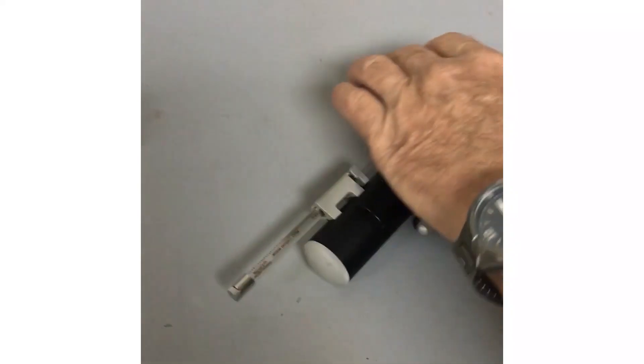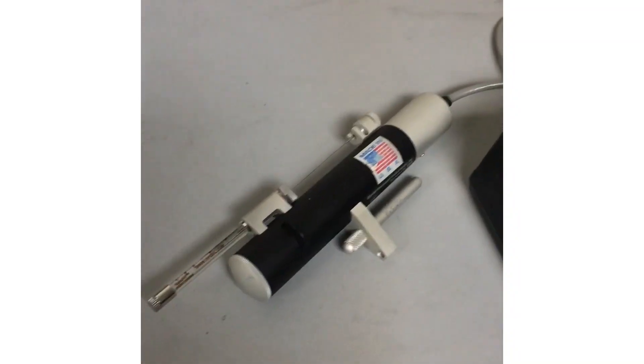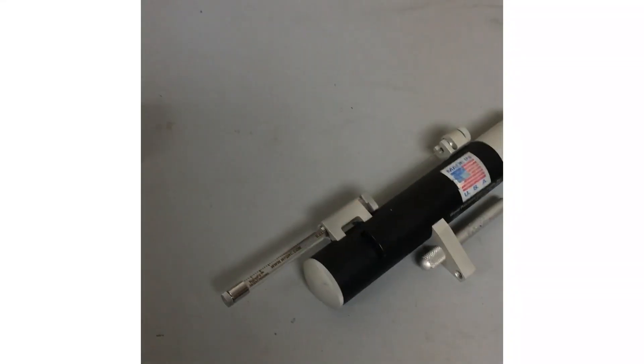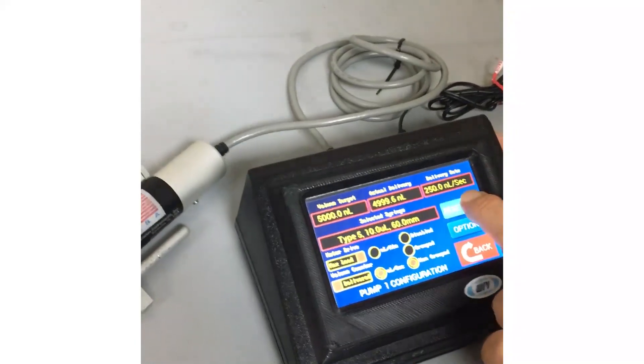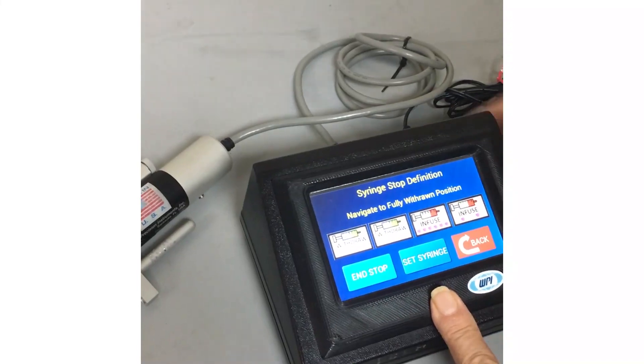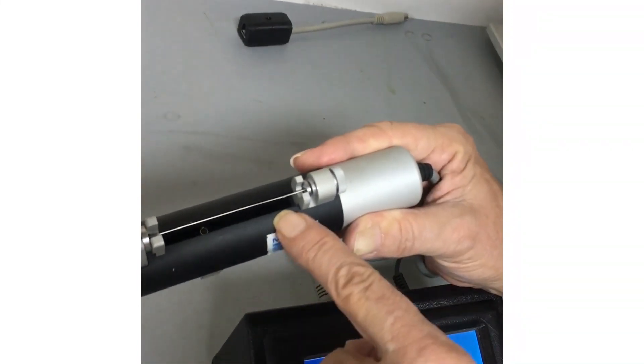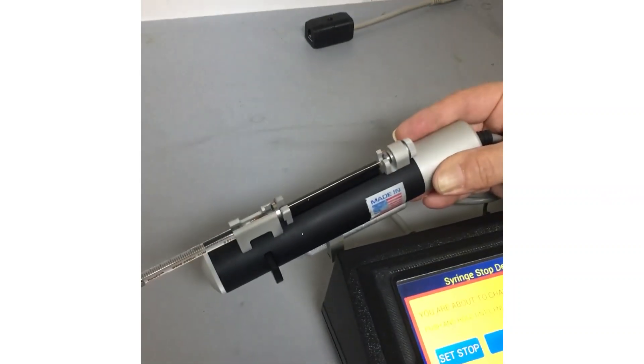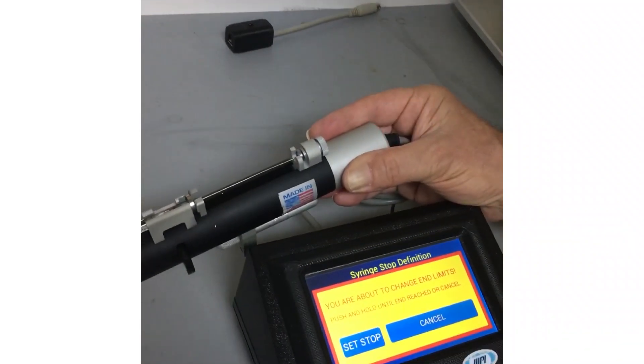The next thing we want to do is set up the controller so it knows where the positions of various locations are in the pump. So we're going to go to reset position, and then this syringe stop definition page comes up. The red light's going to come on when I do this, and we're going to drive — so the red line in the back? Yeah — we're going to drive this carrier that's holding the plunger on the syringe all the way back until the machine does that.